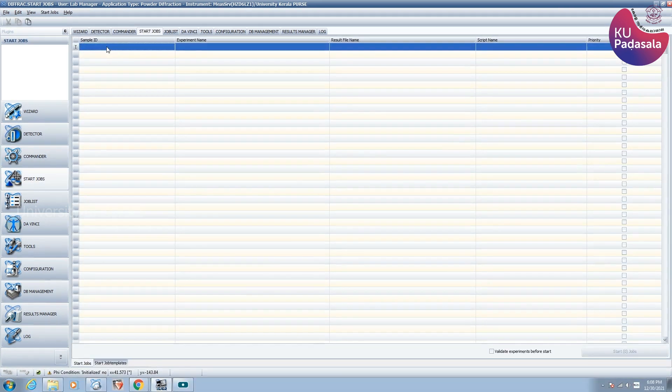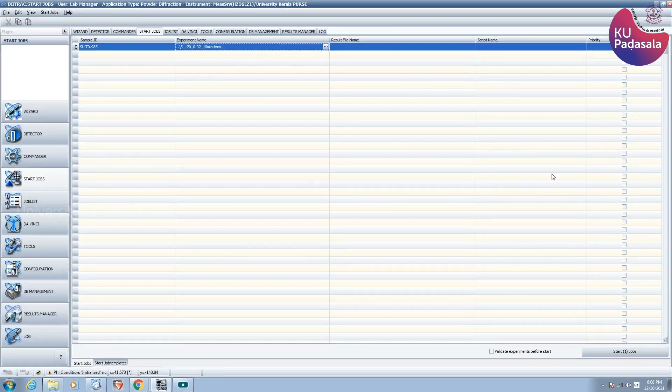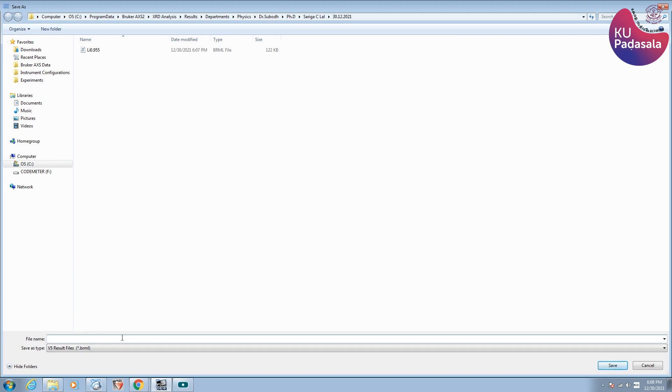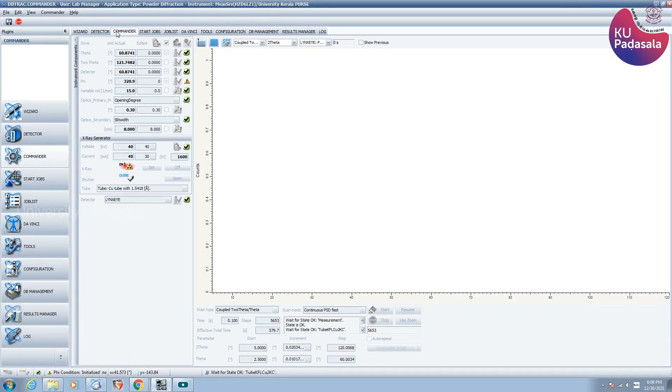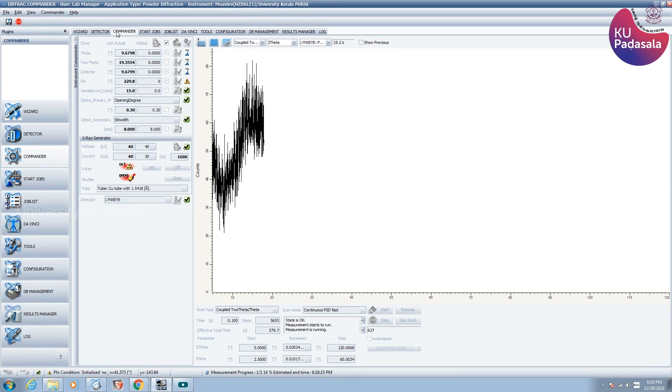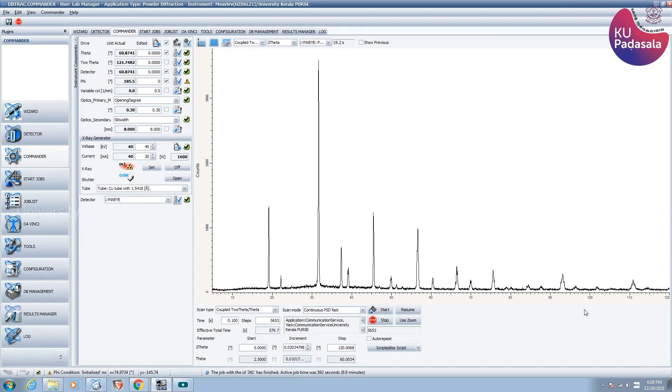To start a scan, use the Start Jobs option from the software. A new window opens. On the first column, enter the sample code. On the next column, enter the required experiment program, followed by entering the path where the spectrum is to be saved. Then start the scan by pushing the Start button. When a scan is completed, the spectrum will be saved as a .raw file or .brml file.